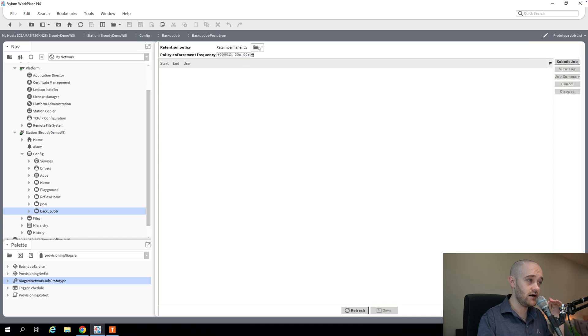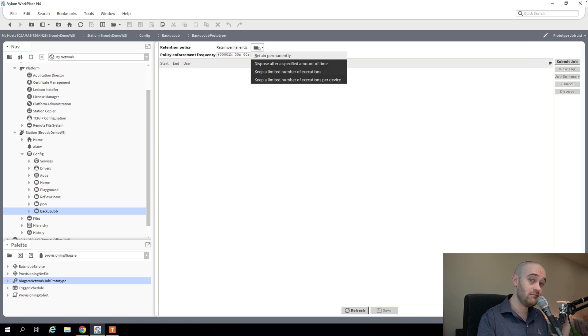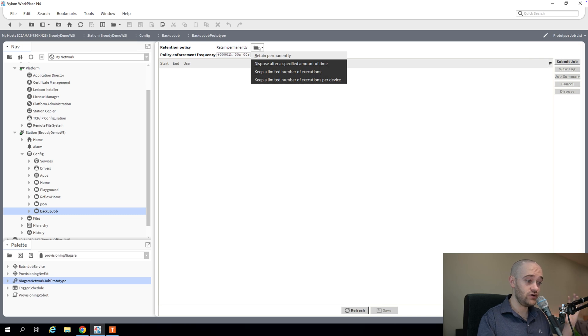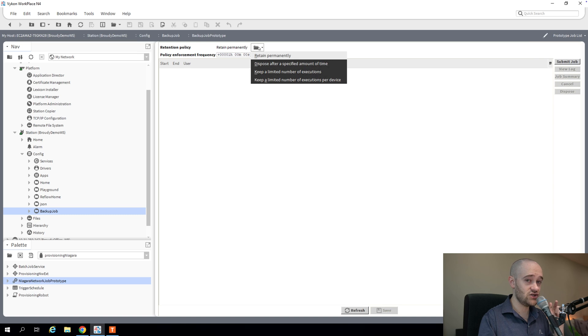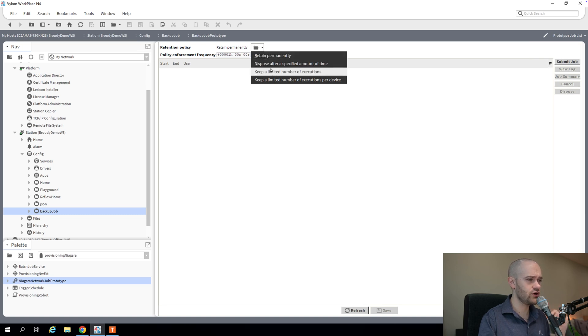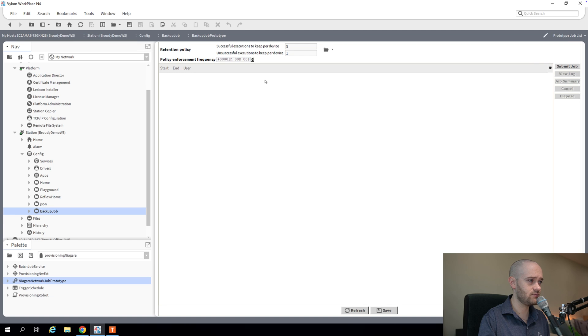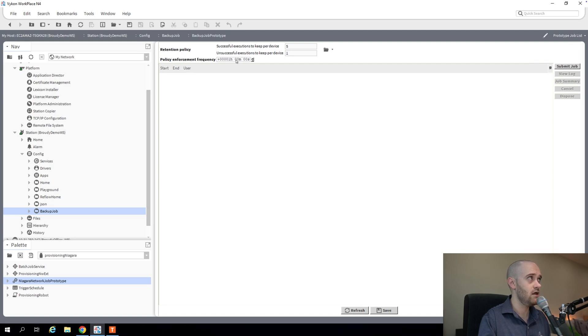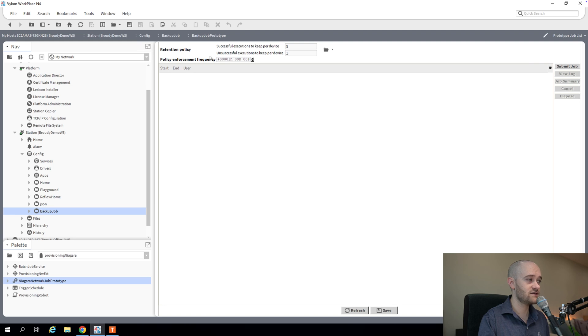And then if I go over to this prototype job list, we can see we have this retention policy. This is super handy if you're doing backups because it allows you to define how many backups you want to keep. Depending on the size of your supervisor and the number of Jaces that are coming up to your supervisor, you could very quickly overload your storage and keep too many backups without changing this retention policy. So what we're going to do is we're going to keep a limited number of executions per device. And I'm going to set this at the default.